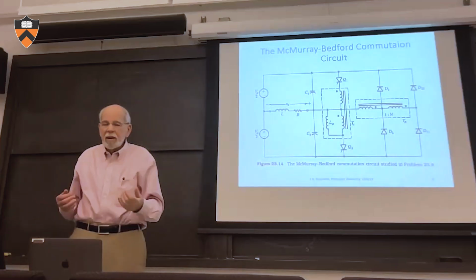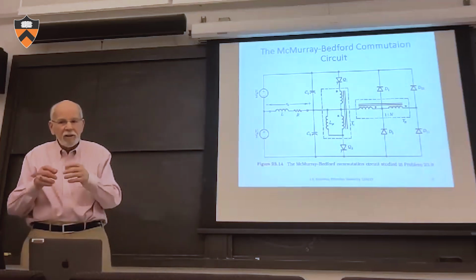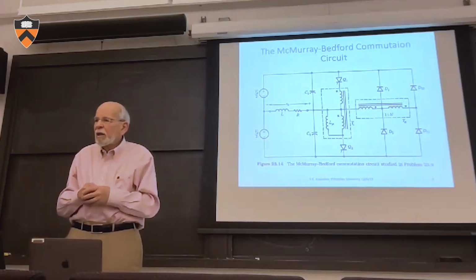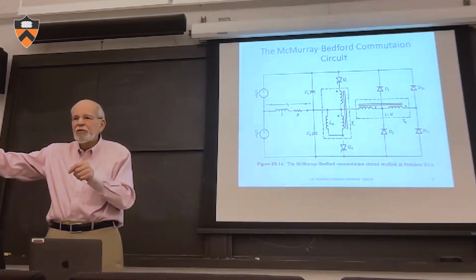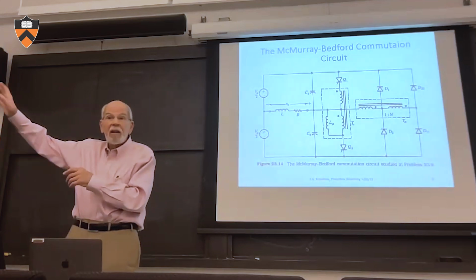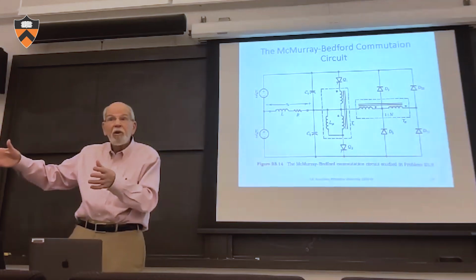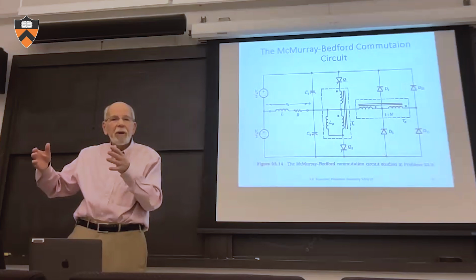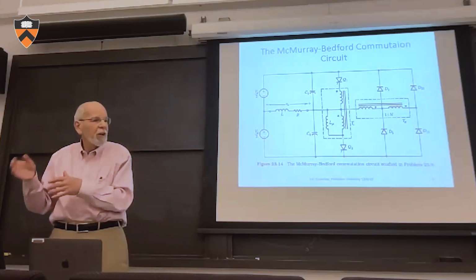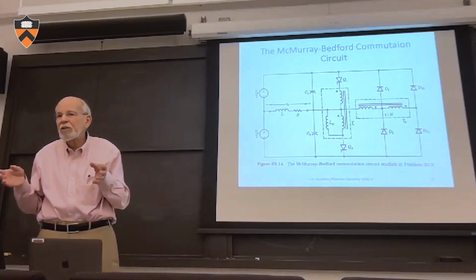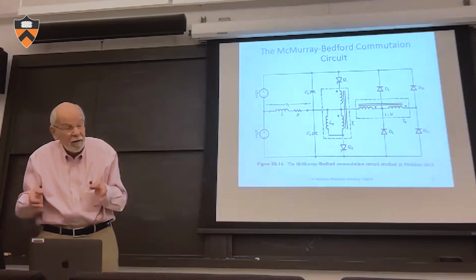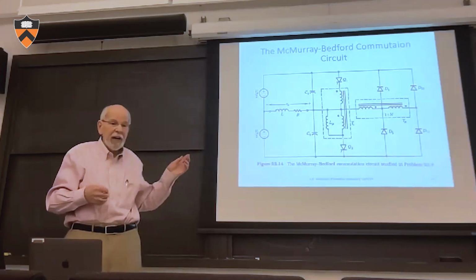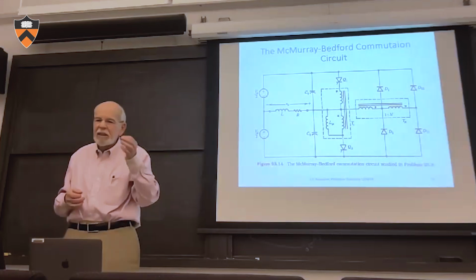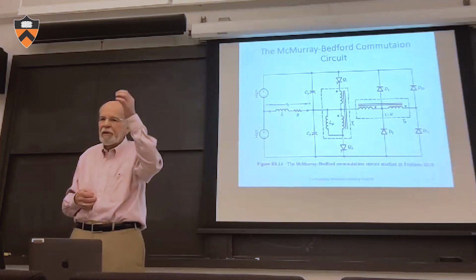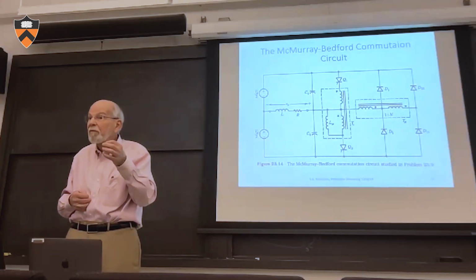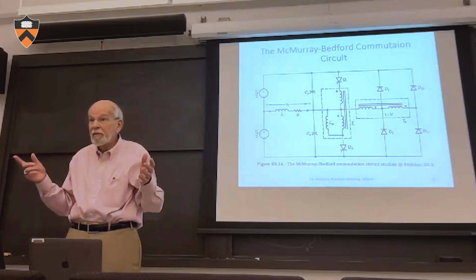So I got the schematic and saw they were using this triac, but the triac was feeding a transformer that generated the high voltage. It was a high ratio transformer, and such a transformer generally has fairly substantial leakage. The other feature of these devices is that they will not continue to conduct once the current drops below a certain minimum value, then they just shut off.